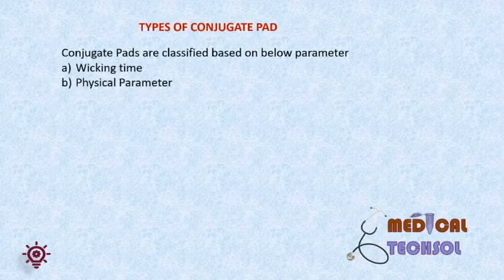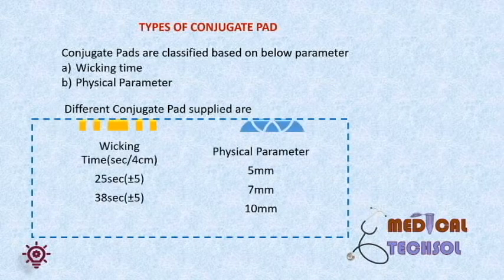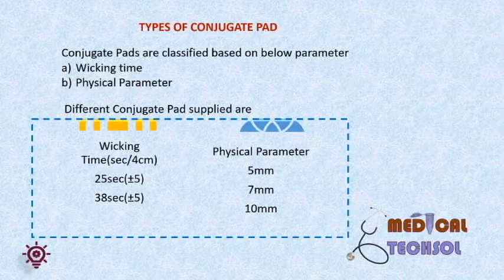Types of conjugate pad. Based on the wicking time and physical parameters, conjugate pads are classified. Wicking time is the time taken to move the sample a definite distance by capillary action, usually measured in seconds. Different conjugate pads are applied based on wicking time — for example, 25 seconds or 38 seconds per 4 cm. Based on physical parameters, 5 mm, 7 mm, and 10 mm conjugate pads are available.